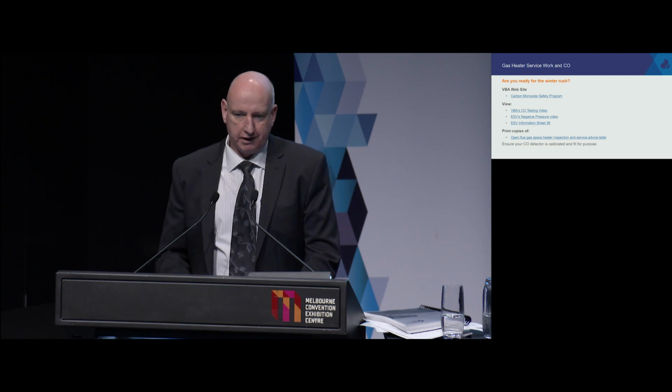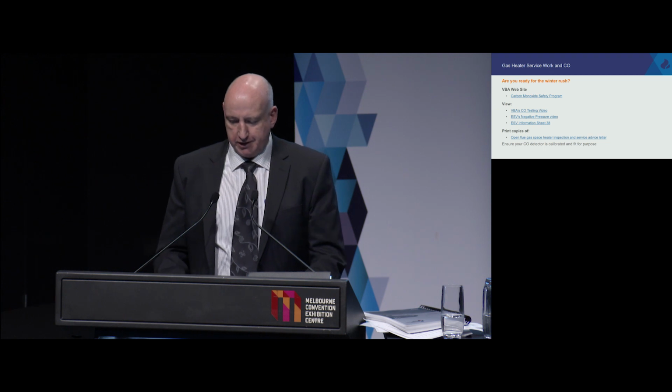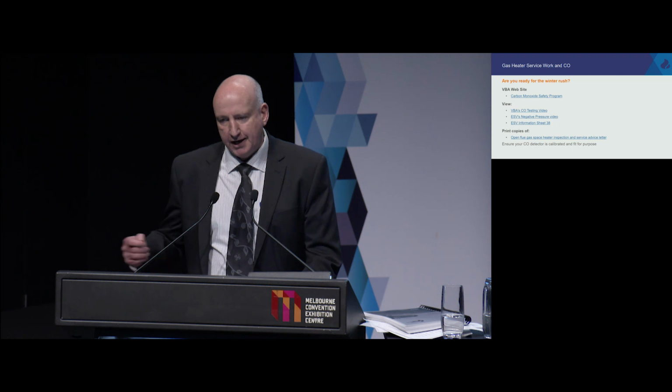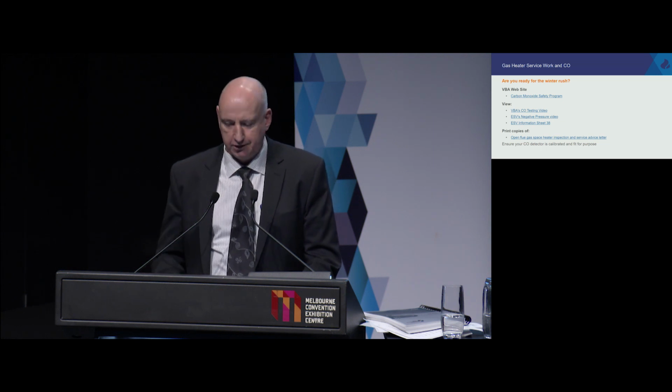So last year, if you don't remember the seminars, it was carry out the negative pressure test. If you had a negative pressure, open the window slightly, get rid of the negative pressure, and then test the heater for CO spillage. And if there was no CO spillage, we had a co-branded letter that said, look, if they won't let you cut the ventilation in to alleviate the negative pressure, then hand them the letter, explain to them the dangers, but it would be okay to leave it on for a very short period of time while you had time to cut the ventilation and so forth, notify the VBA.